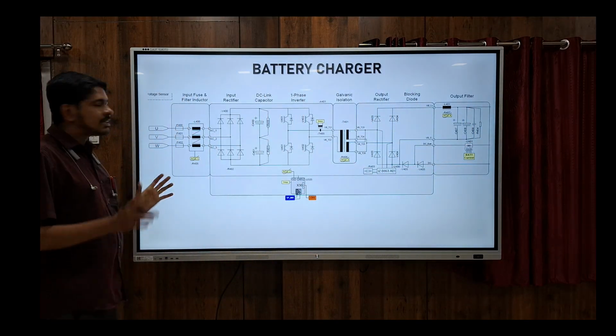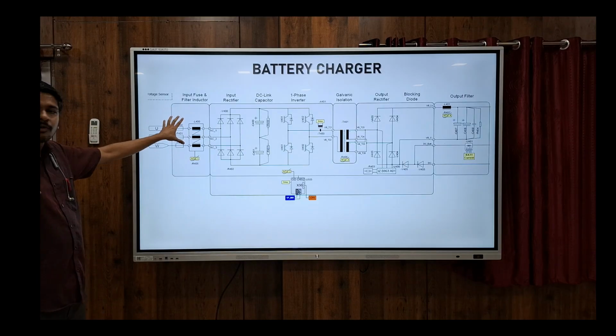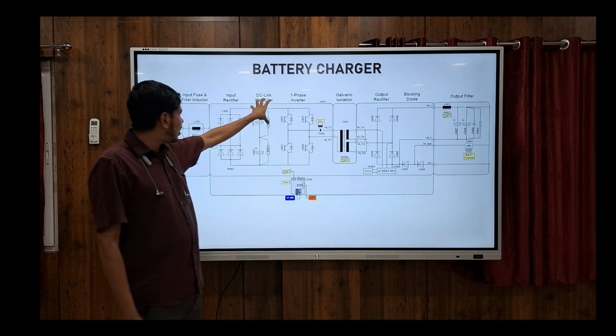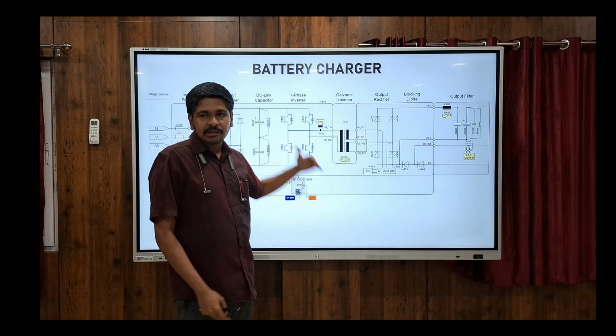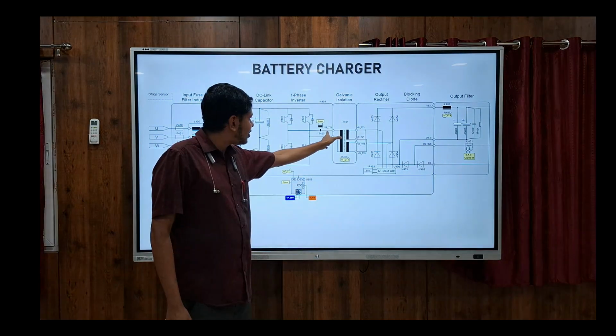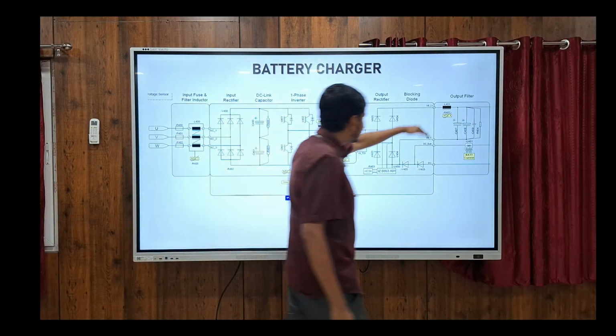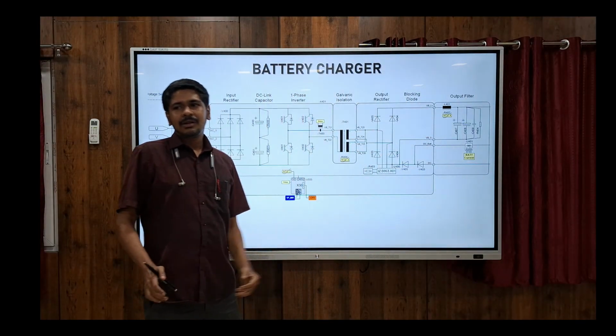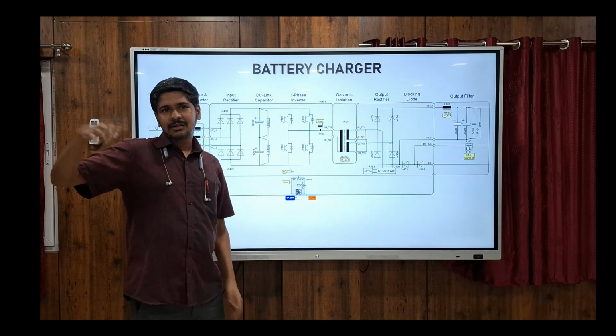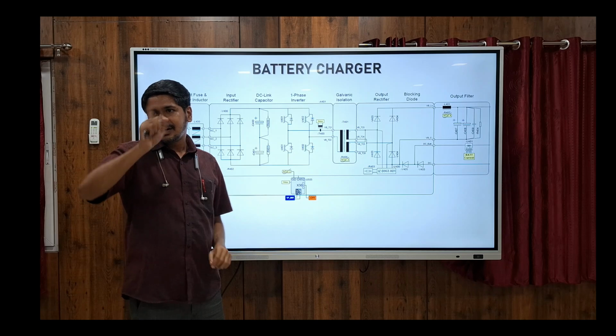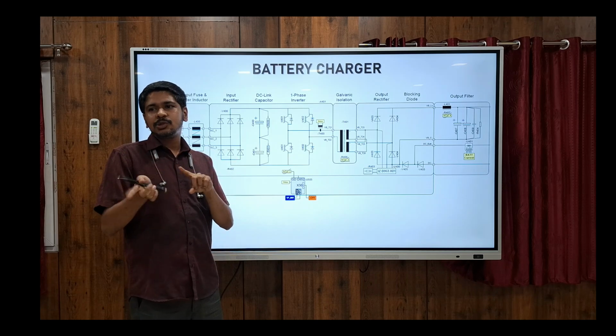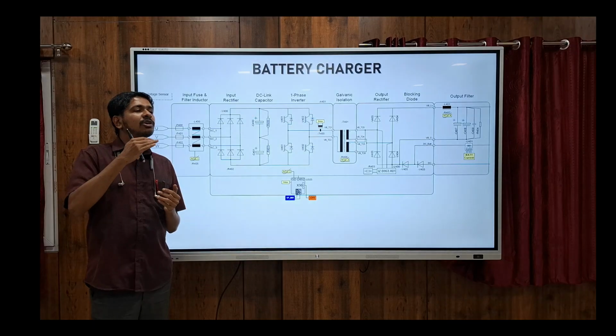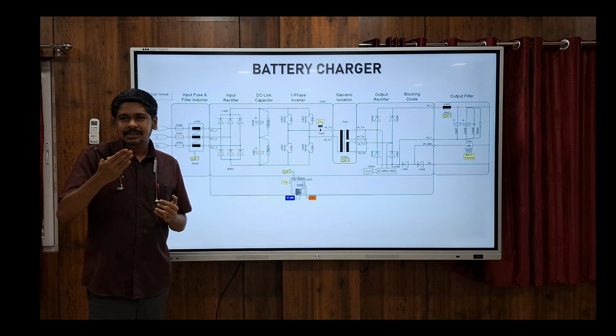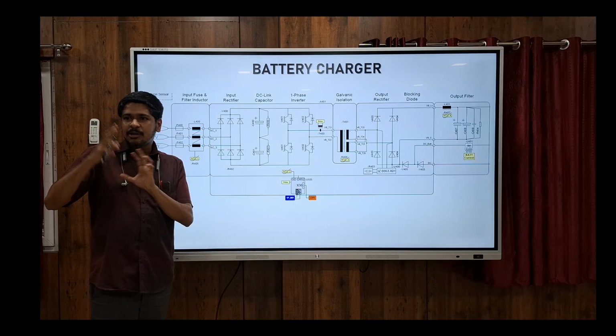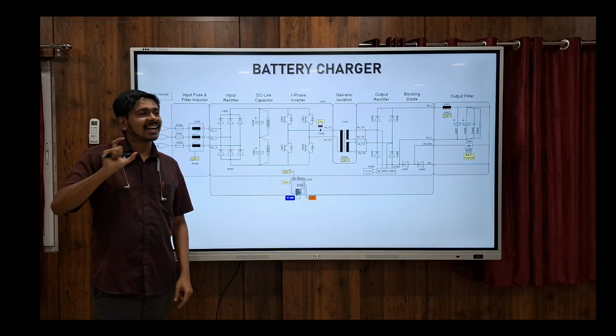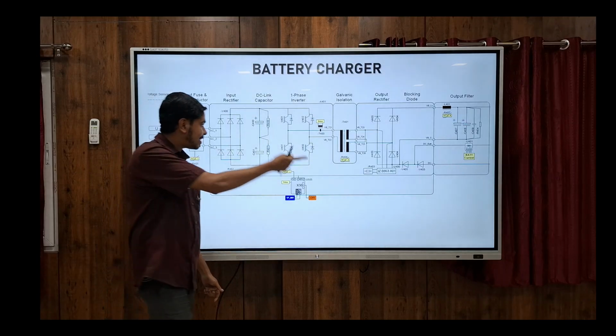Here the sensors incorporated are: input side voltage is measured, then DC link voltage and current will be measured, temperature will be monitored, so the output of this one will be monitored, and on the output side two currents will be measured. One is the total current delivered by it, and the other is the total current returned to the battery circuit, so as to calculate the current delivered by the battery charger and the current taken by the load. The second one is the current taken by battery, which I will explain in the next slide.